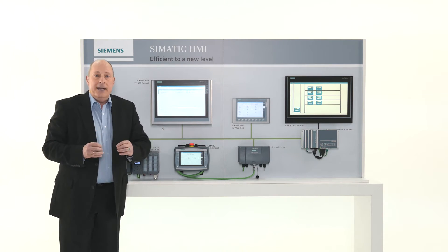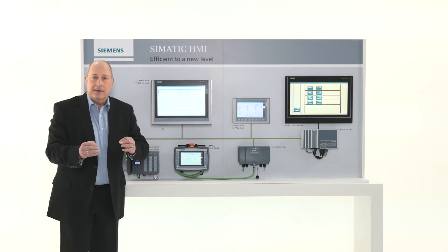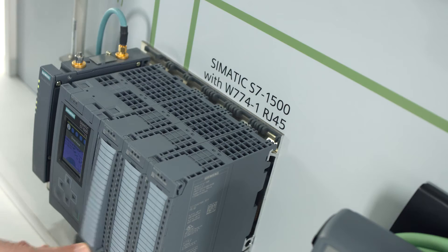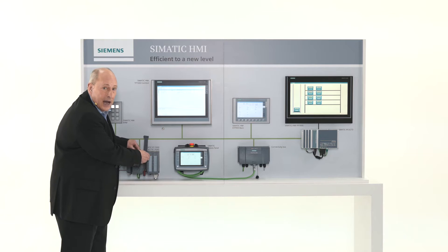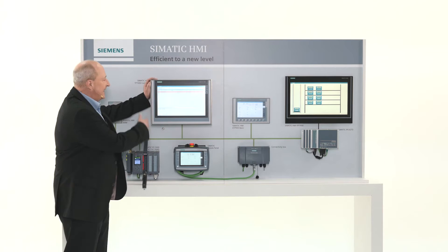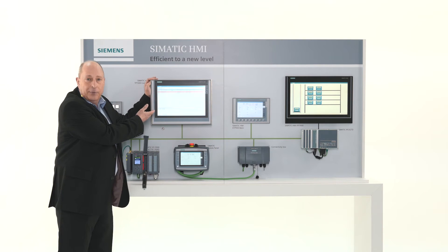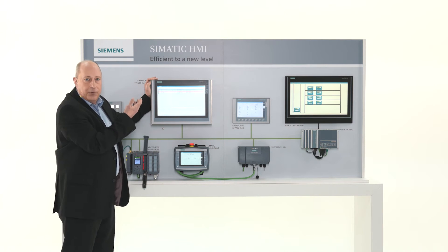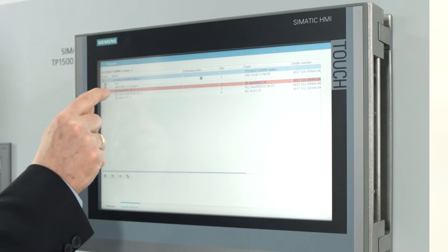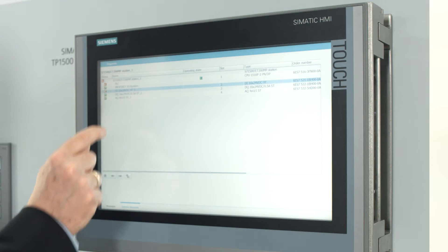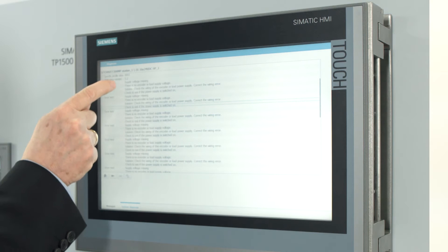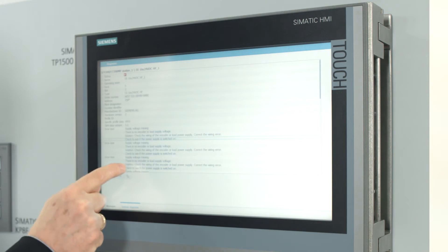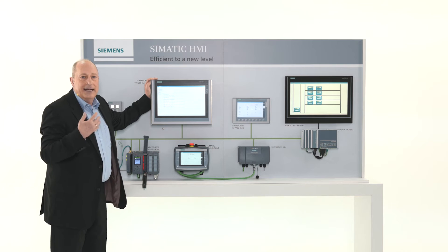I now create a failure — a system error, for example — by removing the power from my digital input module. The system instantly recognizes this and notifies me that a failure occurred. If I want further information, the system delivers it in a way that allows me to determine and fix the failure as quickly as possible.